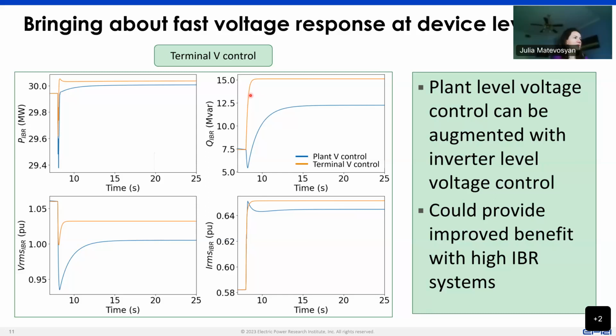Thank you. The next question is, how will all the IBRs on the distribution system impact what you were sharing? Seems like more IBRs reside there. So there is definitely a lot of IBRs on the distribution network. There are gigawatts of inverters on the transmission network, and also in the interconnection queue. What we do see is that the distribution network is going from being a passive network to an active network. And what that results in is increased T&D coordination and increased T&D evaluation studies to try to understand not only if the distribution network inverters can benefit the transmission system, but also if the distribution network inverters could benefit the local distribution network itself with some services, without having to rely on the transmission network.